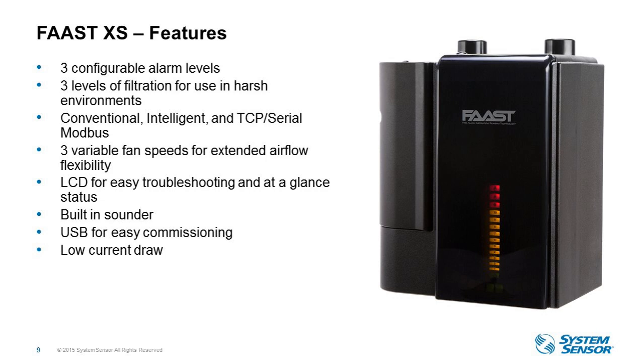Okay, so FAAST XS's flexibility is quite unique. We can program the three levels of sensitivities to match the exact requirements of any project, application, site, or environment. We're not constrained to predefined sensitivities. Because of the adjustable fan speed, we are able to build both extensive pipeline configurations or very small ones. The unique nuisance rejection technologies make FAAST really the best-in-class device when it comes to the areas that we can now use aspirating smoke detection.